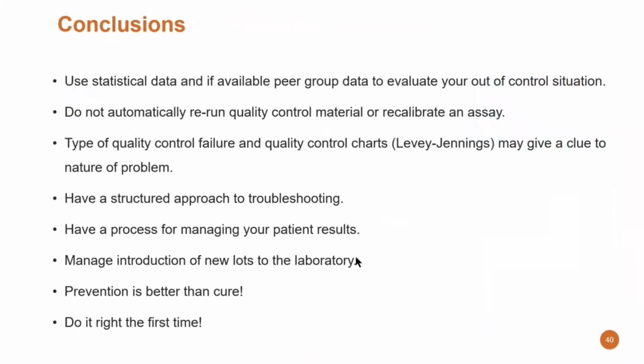So now my conclusion: use statistical data and available peer group data to evaluate your out of control situation. Do not automatically rerun quality control material or recalibrate the assay. So if you don't know the reason and you just rerun the QC material, it may deliver the same result, doesn't help you to fix the problem, and you have to see what the error is and fix the error first, the problem first. The same is true with the calibration.